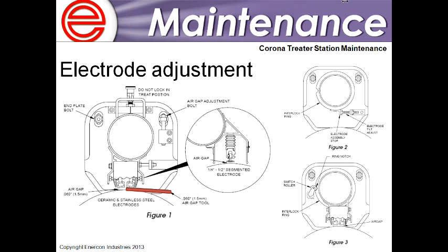The stop bolt can be adjusted in or out to adjust the pitch of the electrode assembly. If you remember from that slide a few slides back that showed a misadjusted electrode gap, that was actually due to the pitch or the tilt being off of the electrode assembly. So the stop bolt would be adjusted to adjust basically where that's going to stop as the electrode rotates open and closed. And then basically figure 3 is showing the electrode limit switch.